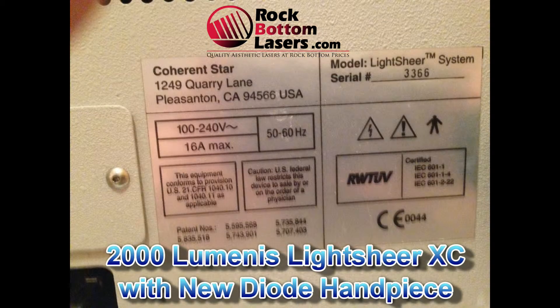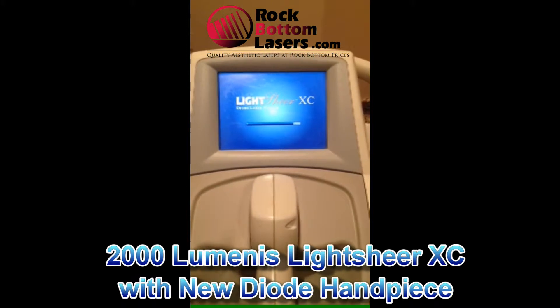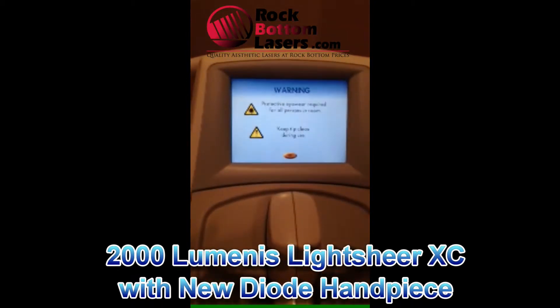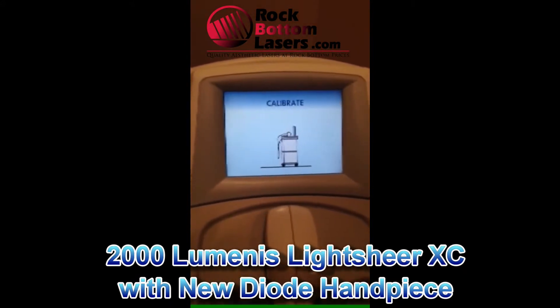And that number — the best you will ever see for headroom is 1.8 to 1.9 in some cases, but the standard headroom even on a new machine is only around 1.5 or 1.6, so this is very good headroom on it. It has 1.5 million original pulses on the system and it's in excellent cosmetic condition and excellent operating condition.